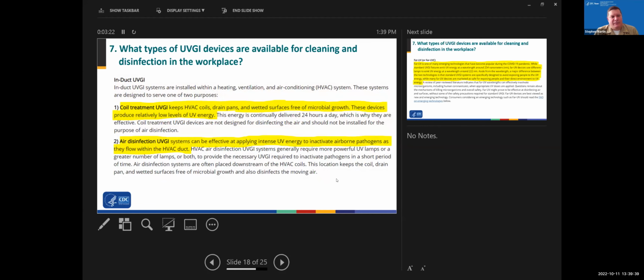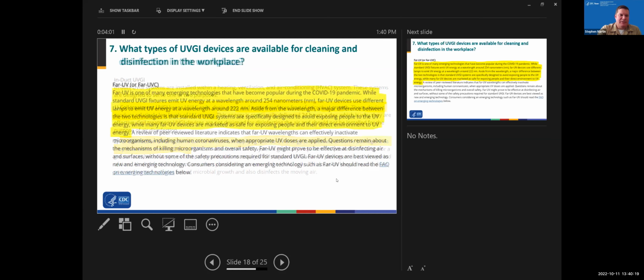In-duct UV is where you mount UV lights inside your air handling system or inside an air duct somewhere. I will caution you, there are 2 types of in-duct system. One is for coil treatment. So if you go into your local big box hardware store and you buy a UV light to mount in-duct, there's a 99.9% chance that is for coil treatment only, and it'll do you very little good for air disinfection. Air disinfection in-duct systems can be designed to be very, very effective and efficient, but they typically have to be custom designed for your HVAC system by qualified HVAC system designers.